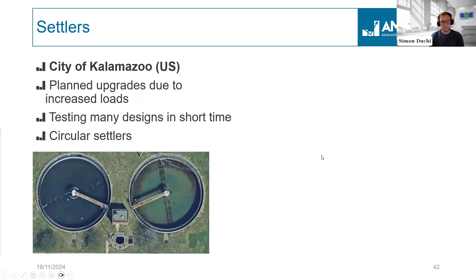So they came to us with certain designs that they wanted to test. We tested a lot of different designs that they had in mind, and also we had some brainstorms together. Can we optimize these settlers? We're talking here about circular settlers. So that's the first case. The second case were rectangular settlers in Sweden of Uppsala Vatten, a utility. And that was a bit different. They had a problem with sludge washout during high flow.